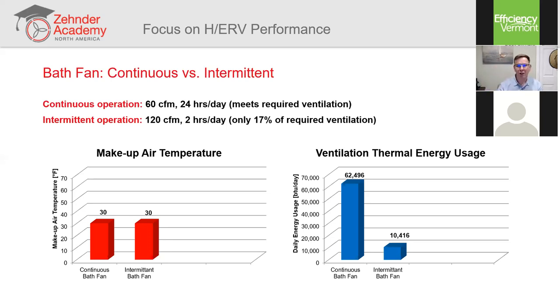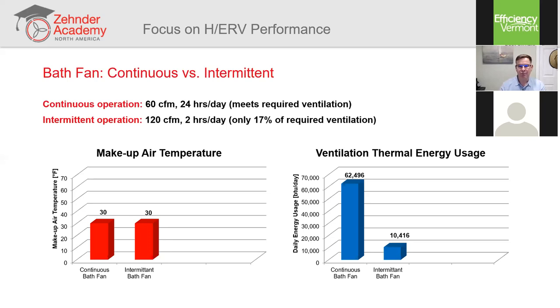With a continuous bath fan at 60 CFM and a 40-degree lift from 30°F to 70°F, you're looking at 62,000 BTUs per day. If instead you use the bath fan intermittently — two hours a day at 120 CFM — you're only getting 17% of your required ventilation, with makeup air still coming in at 30 degrees. You've reduced the heating cost, now looking at only 10,000 BTUs per day.